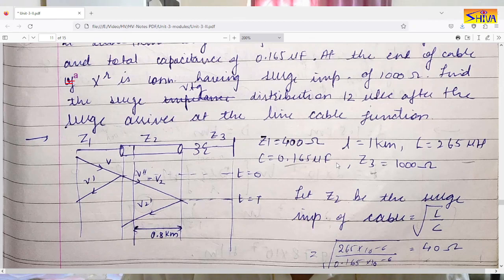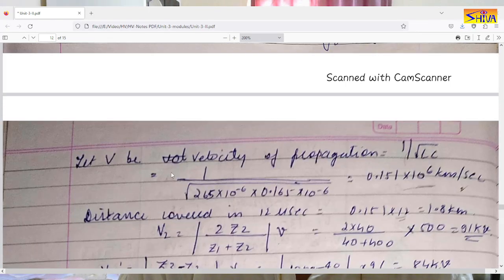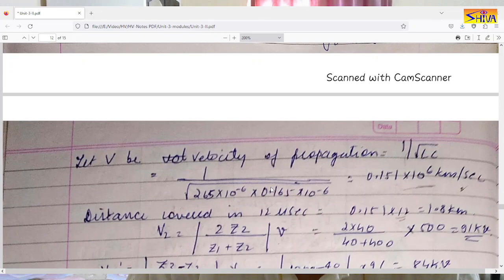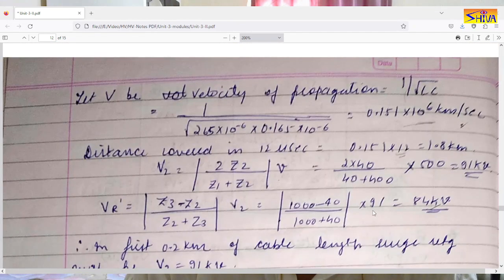With all surge impedances known, the velocity of propagation in the cable is 1/√(LC). Substituting the values for L and C, the velocity is 0.151×10⁶ km/s. The distance covered in 12 microseconds is 12 × 0.151×10⁶ = 1.8 kilometers. Since the cable is only 1 km long, the wave has reached the transformer end and the reflected wave has traveled back 0.8 km into the cable.